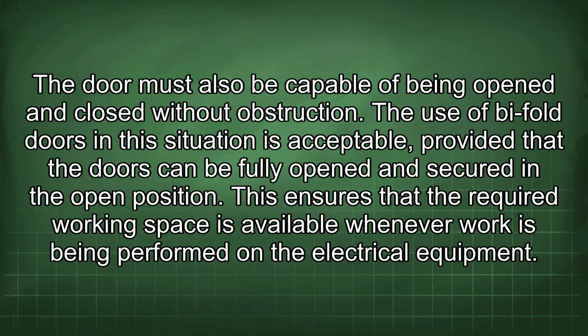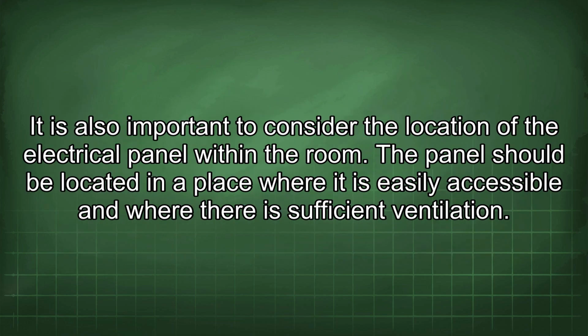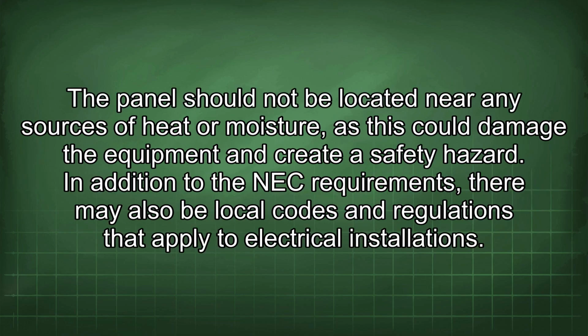The use of bifold doors in this situation is acceptable provided that the doors can be fully opened and secured in the open position. This ensures that the required working space is available whenever work is being performed on the electrical equipment. It is also important to consider the location of the electrical panel within the room. The panel should be located in a place where it is easily accessible and where there is sufficient ventilation.